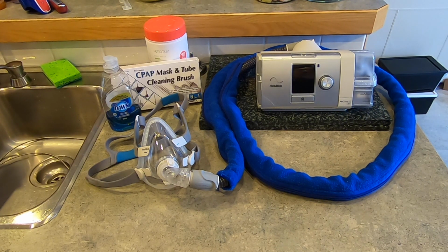So as you can see from my video, cleaning your CPAP equipment is neither difficult nor time consuming and can be accomplished with some basic tools and supplies. My recommendation for cleaning intervals is once per week for the water reservoir, once per day for the mask using some CPAP wipes, as in wiping it down, and then cleaning the hose and headgear on a monthly basis. More so if you have either oily hair or live in a dusty environment. And most importantly, make sure that you service your CPAP filter at least once per month.